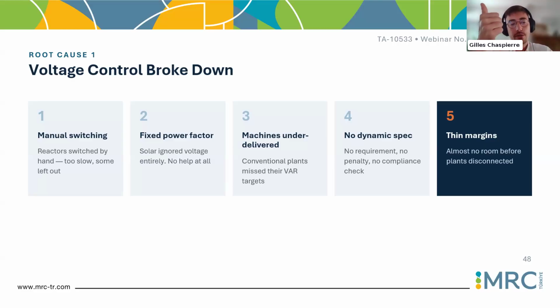The first thing is the manual switching. I mean, in an era where voltage is moving very fast, we have more and more situations with power electronic converters, renewables, meaning that the voltage is less and less stiff, it can move a lot. Manual switching of shunt reactors is no longer acceptable. It's too slow, basically. In 84 seconds, it was too slow to take the decision, to click on the button and to make sure the shunt reactor would be back on time. You need to have something automatic at the point of connection of the shunt reactor that will measure the voltage, and if it goes outside of some margin, automatically disconnect or connect the shunt reactor.